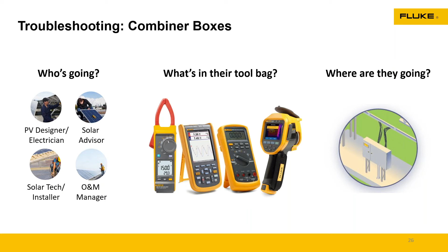The tools used here are pretty basic: a clamp meter to measure current, maybe a regular DMM to measure voltage and current, a scope, and a thermal imager. The combiner box is the key component tying everything together before it goes to the inverter. It has fuses, and this is where I can check for ground faults. A technician can go out and check all of the legs to make sure everything is balanced.